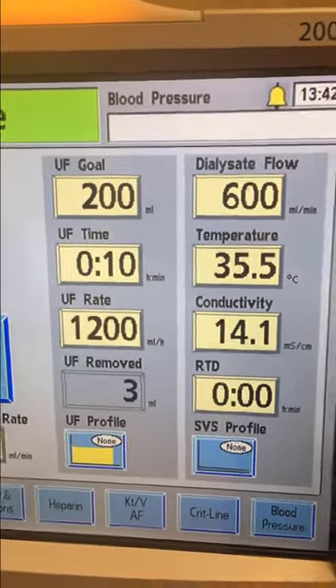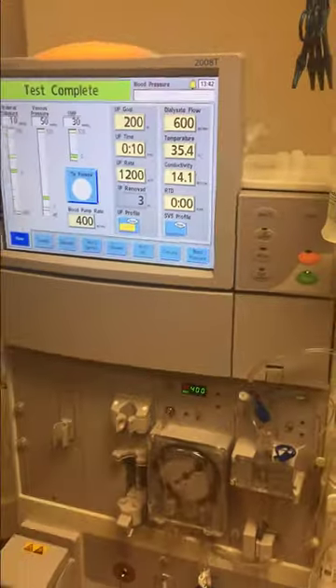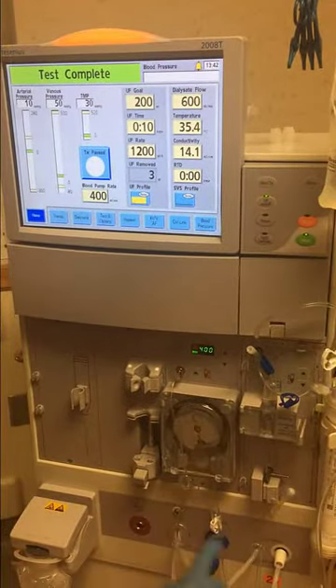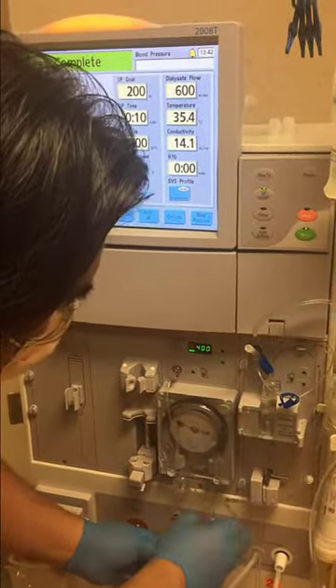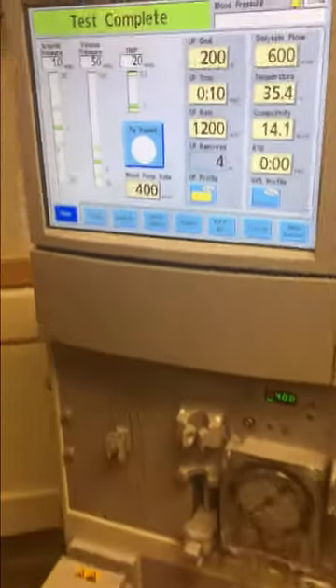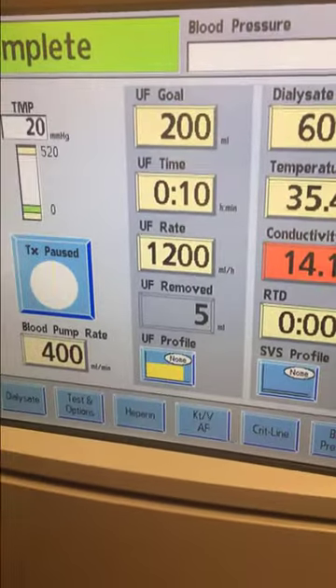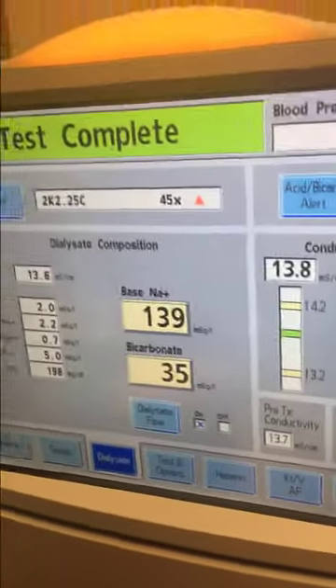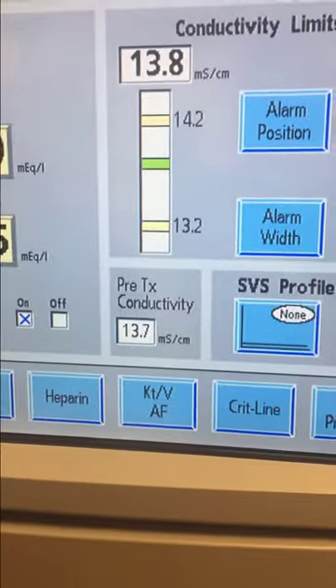And then we turn the pump speed up so the pump can be set at 300 to 400 milliliters per minute. And that will just recirculate saline through the machine. It will draw saline across the dialyzer. It helps make sure that any residual sterilant or air that we have inside of that dialyzer gets rinsed out.